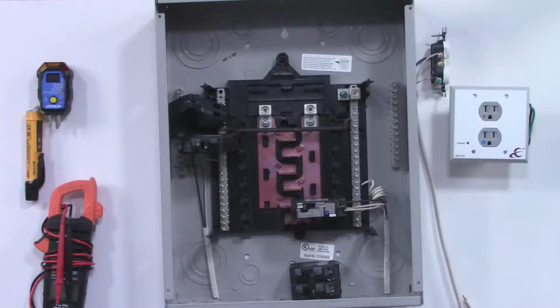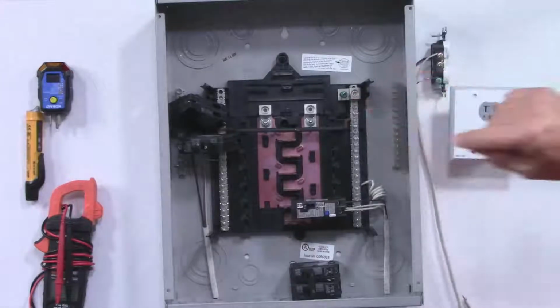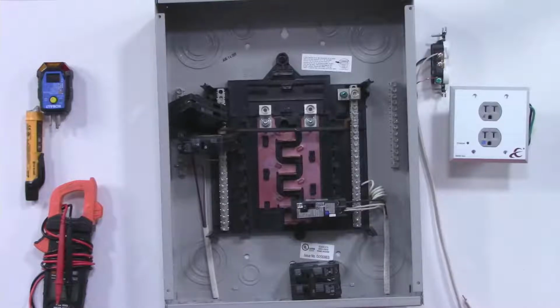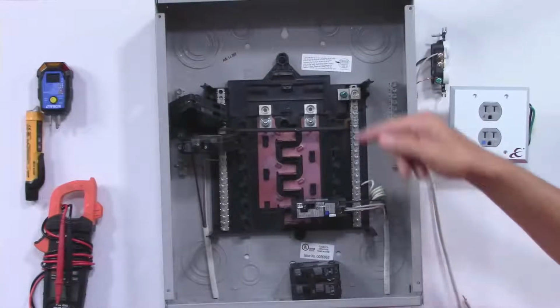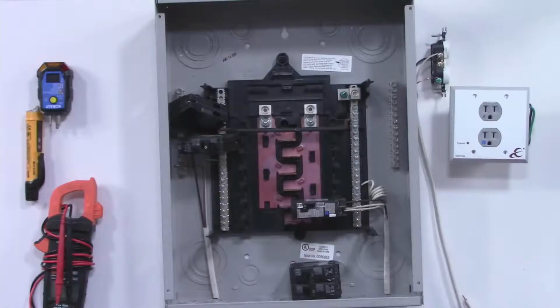Okay, that's important. So don't think about going 2, 4, 6, 8, because it's 1, 3, 5, 7, 2, 4, 6, 8, correct? Correct. So when you're looking at it side by side, they can actually be on different phases. Yes, so one right underneath the other is a different phase. So you actually want to go across, 1 and 2, not up and down.